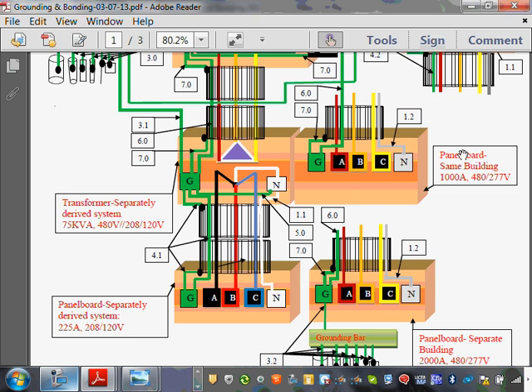Now coming out of the secondary side, the first thing you need to do is bond the newly created neutral. This is a newly created, owned and operated neutral. That's not the one the utility gave you, right? You created that neutral, you own it, operate it, and maintain it. So here's my newly created neutral. You have to bond the neutral to the ground. So you bond it all the way here to the ground, and we take it all the way to the same reference.